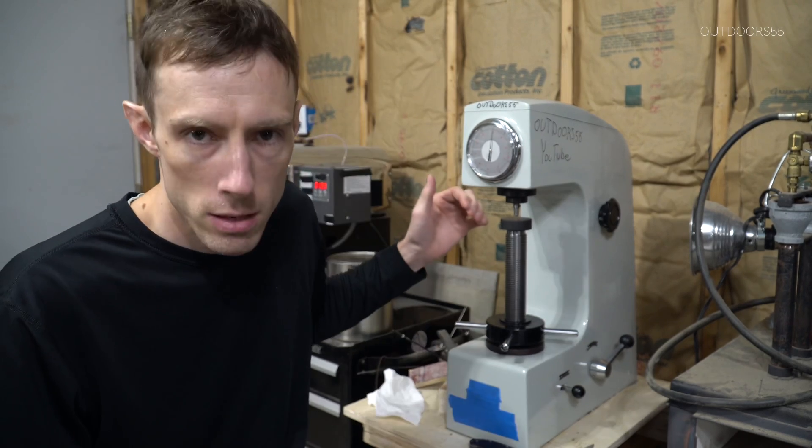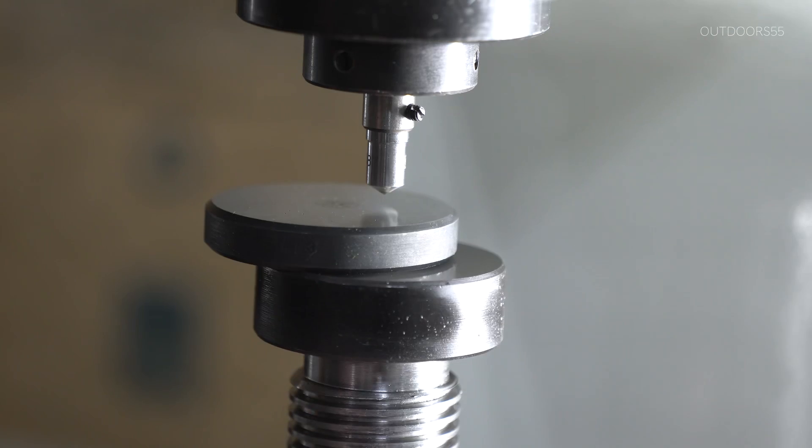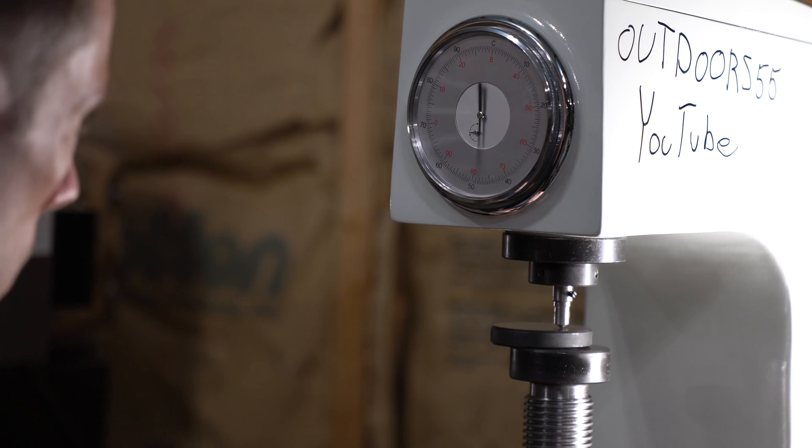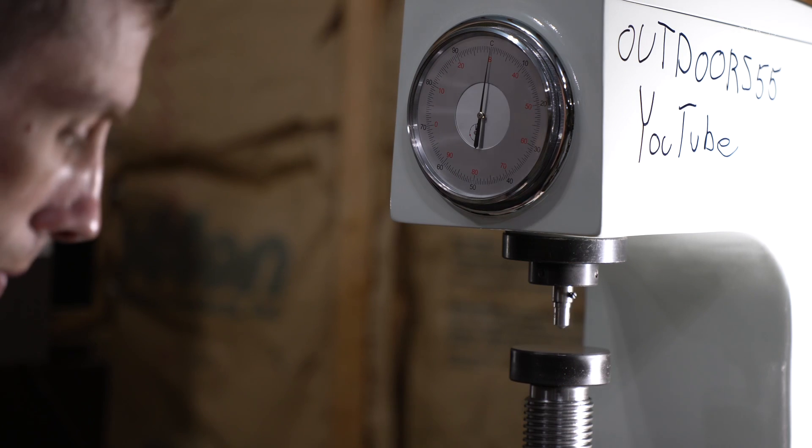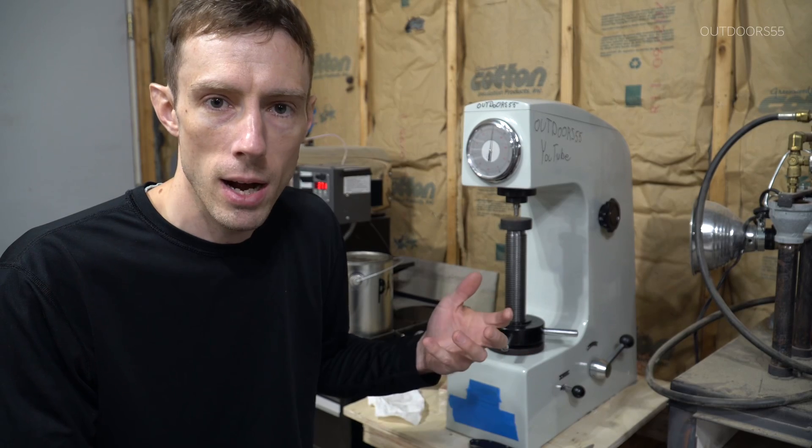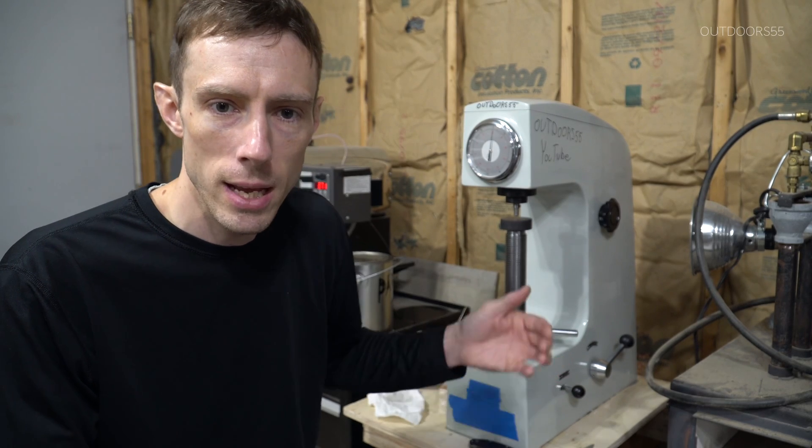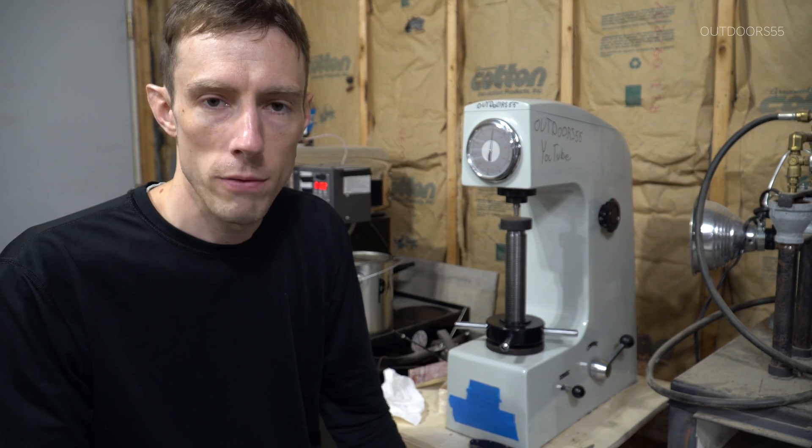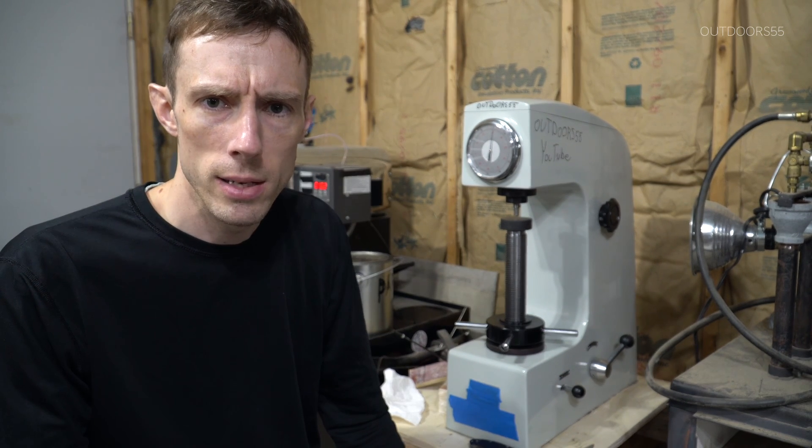As always, the hardness tester has been calibrated multiple times on multiple different test blocks, as well as I will be analyzing each test result against other test results that I have previously completed and comparing all of those results to help maintain accuracy. So without further ado, let's get to the overview and the testing.